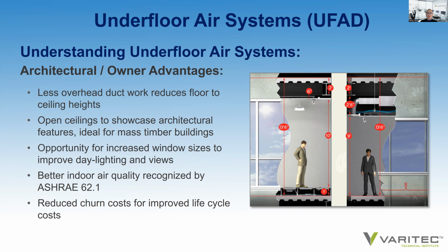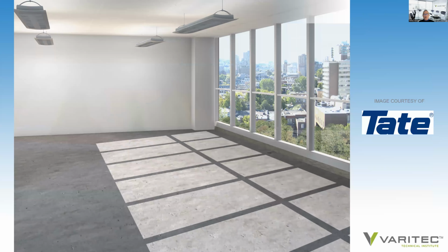If an owner wants to remodel an open floor area, changing ductwork locations is not required. Moving 2x2 panels may be desired. It's a lot easier than changing out ductwork. You don't even have to readjust the diffuser sizes necessarily for those applications. So there's an attractive life cycle cost advantage for owners who adopt underfloor air systems. So what do these systems look like?